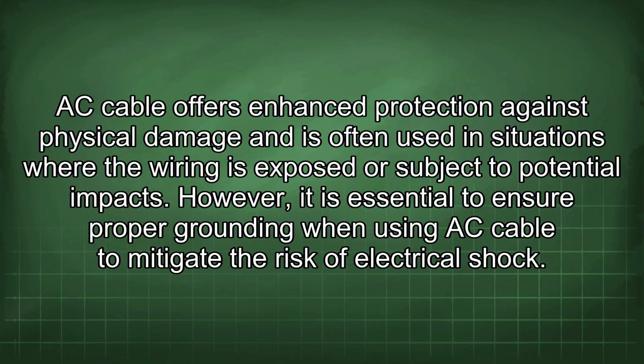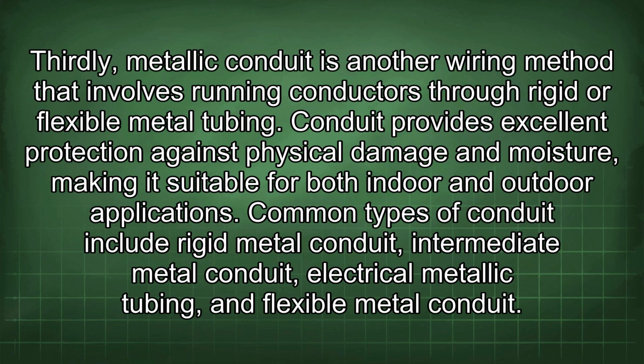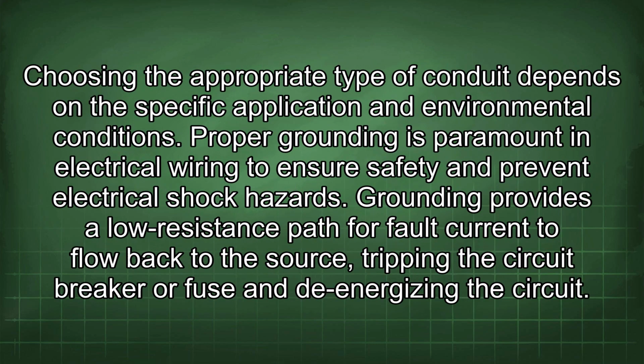of electrical shock. Thirdly, metallic conduit is another wiring method that involves running conductors through rigid or flexible metal tubing. Conduit provides excellent protection against physical damage and moisture, making it suitable for both indoor and outdoor applications. Common types of conduit include rigid metal conduit, intermediate metal conduit, electrical metallic tubing, and flexible metal conduit. Choosing the appropriate type of conduit depends on the specific application and environmental conditions.